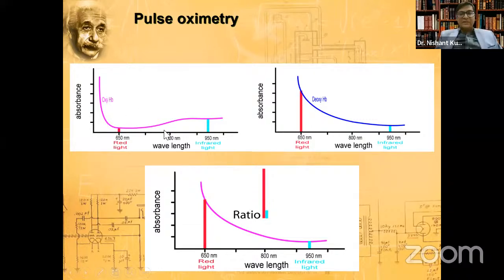So if we combine these two figures, infrared light is absorbed more by the oxyhemoglobin and red light is absorbed more by the deoxyhemoglobin. So if the concentration of deoxyhemoglobin is more, red light will be absorbed more, and if the concentration of oxyhemoglobin is more, infrared light will be absorbed more. The detector plate detects how much of the red light and how much of the infrared light is being absorbed, and based on that ratio, using mathematical formulae and algorithms, it gives us the value on the monitor.